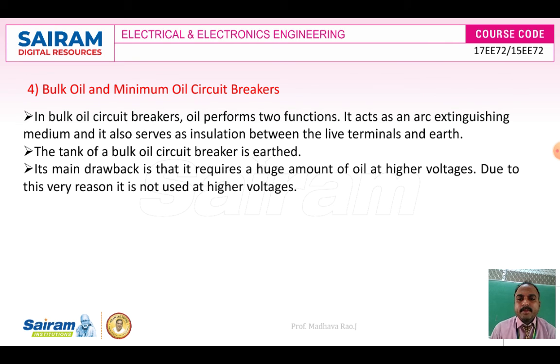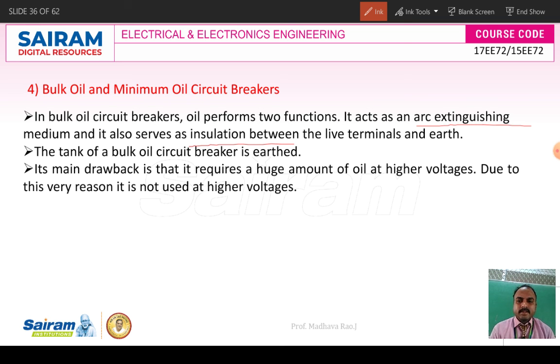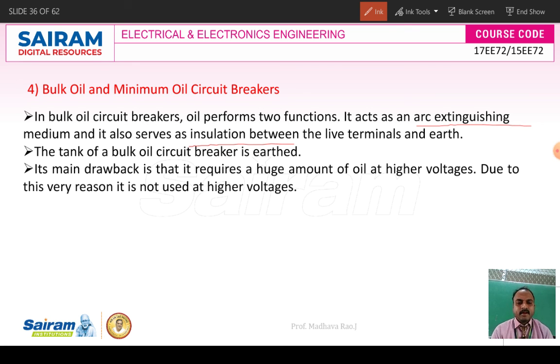In bulk oil circuit breakers, oil performs two functions: arc extinguishing and insulating between the live terminals, contacts, and earth. The main drawback of bulk oil circuit breakers is that a large amount of oil is required at higher voltages. Due to this reason, these circuit breakers are not used for higher voltages.